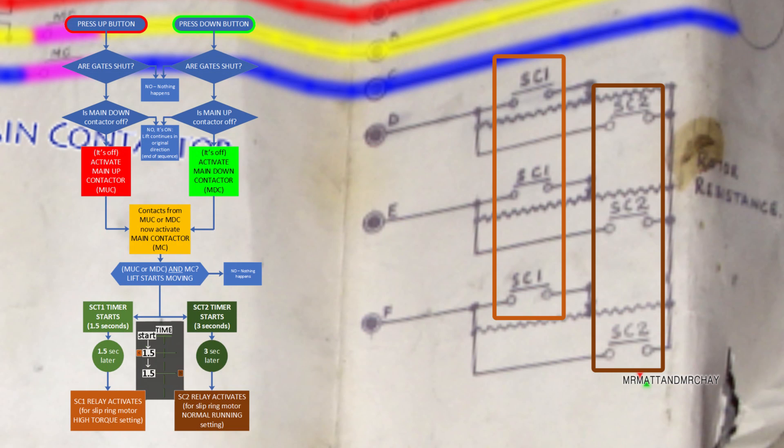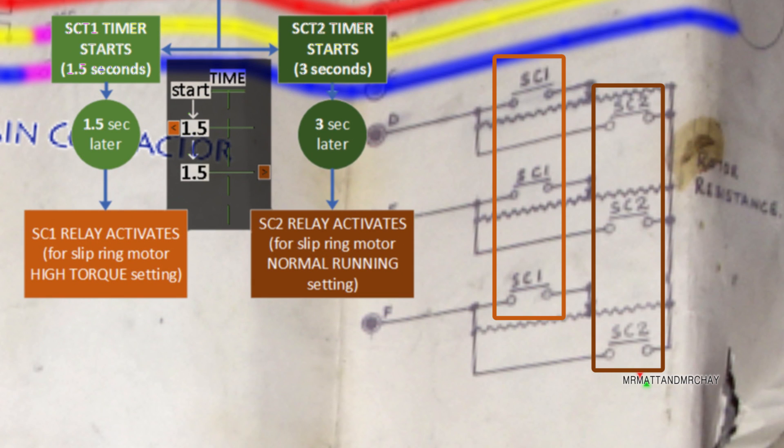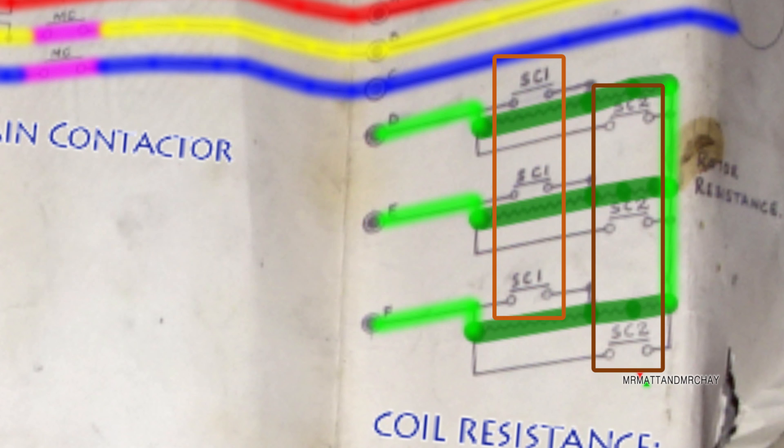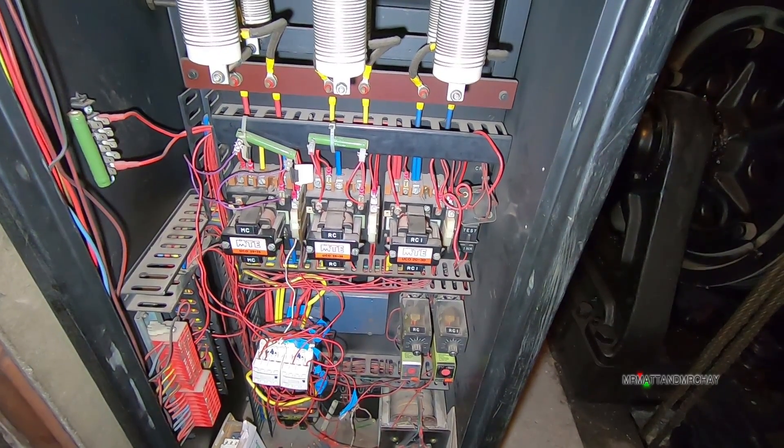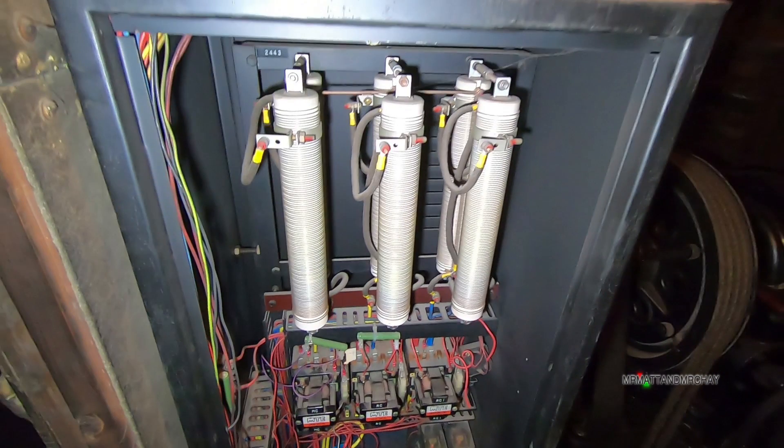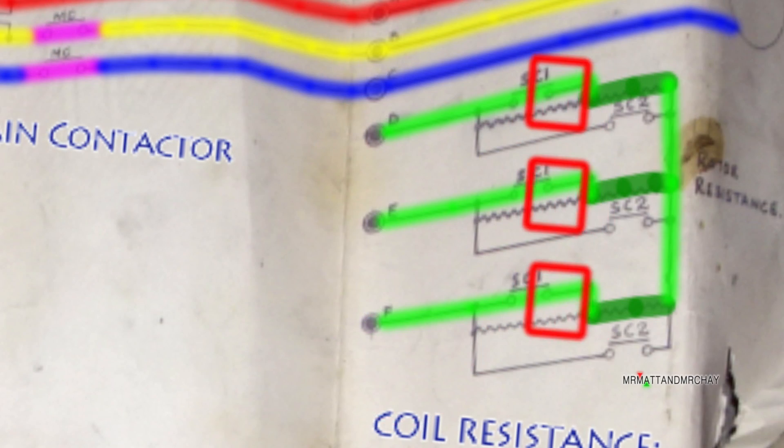If you remember, these are both linked to timers and both delayed by one and a half seconds each when the motor received power, connecting D, E and F together, but via three separate resistors. After one and a half seconds, SC1 activates. These can be adjusted to provide more or less resistance for fine tuning by moving these rings up or down. This configuration creates the torque advantage to get the motor up and running.